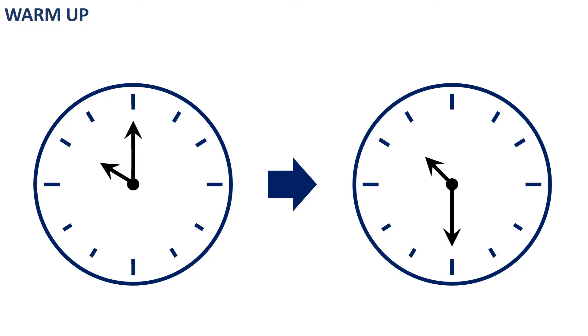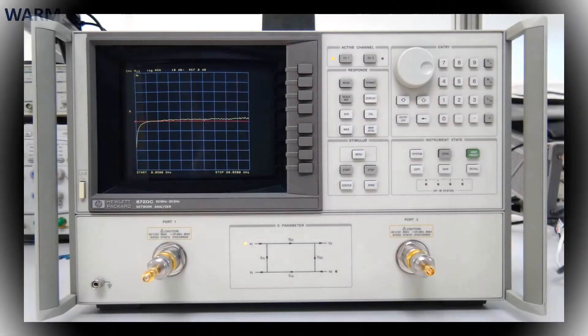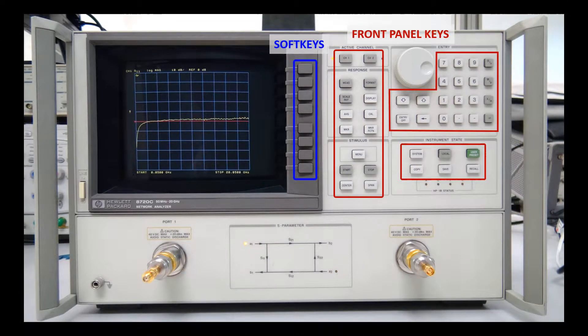You should calibrate only after at least 30 minutes of warm-up time to let the instrument reach good thermal stabilization. We control the analyzer with front panel keys and soft keys. The specific function of each soft key depends on the menu you choose with the front panel keys.